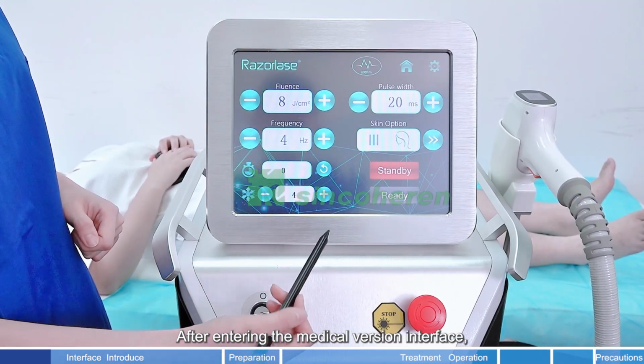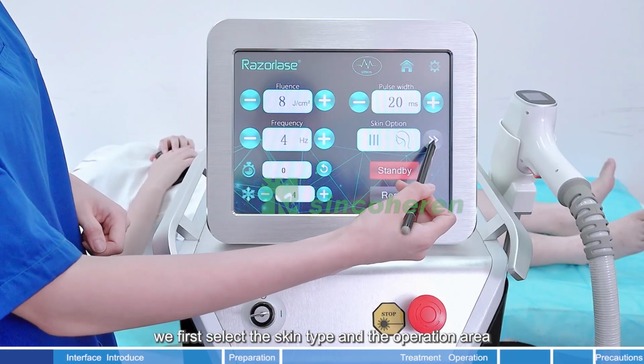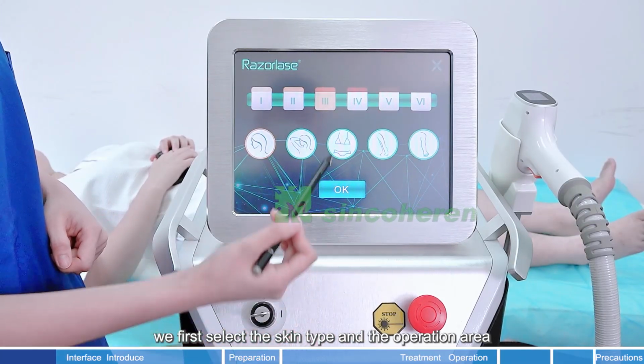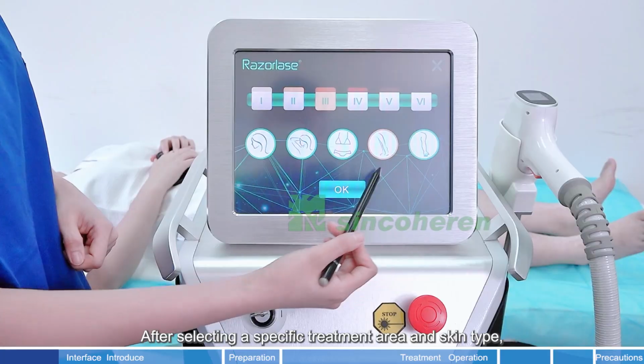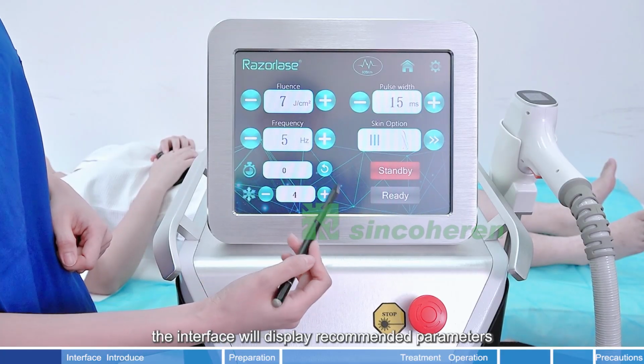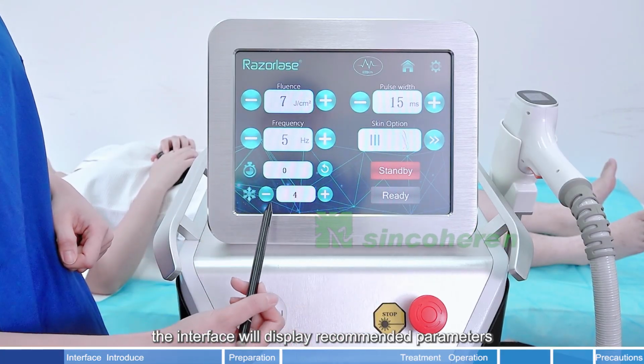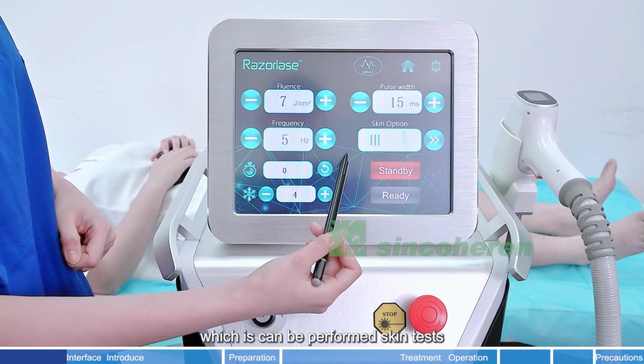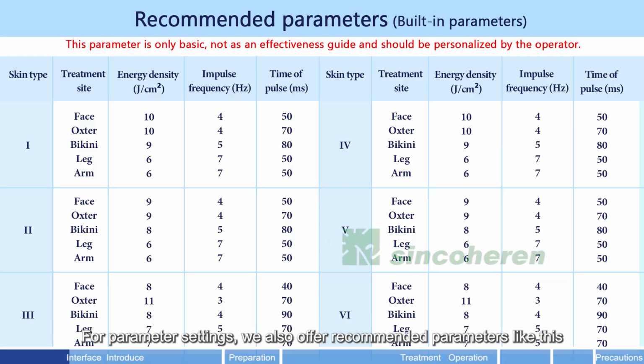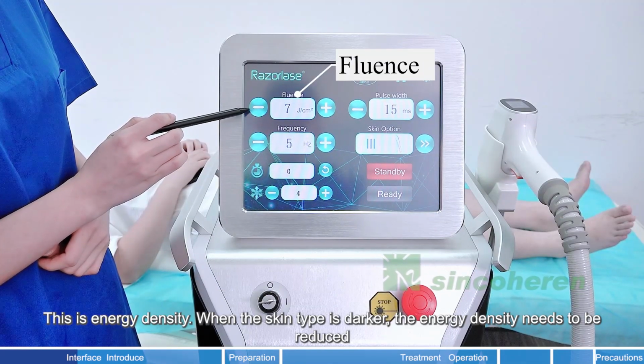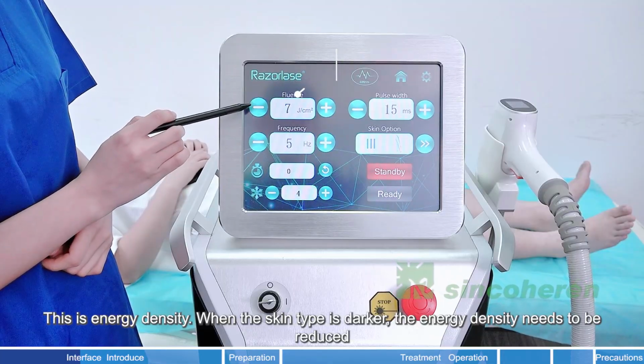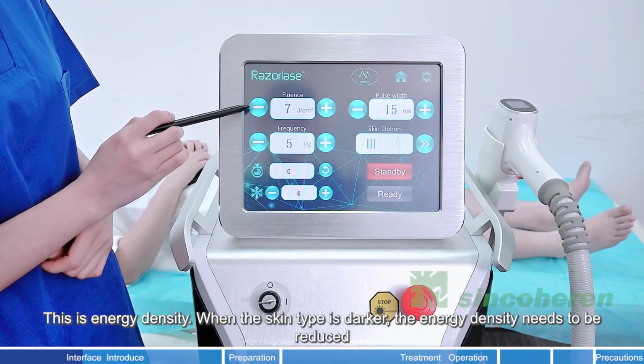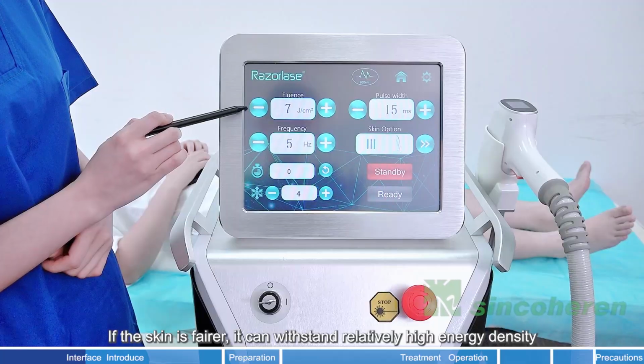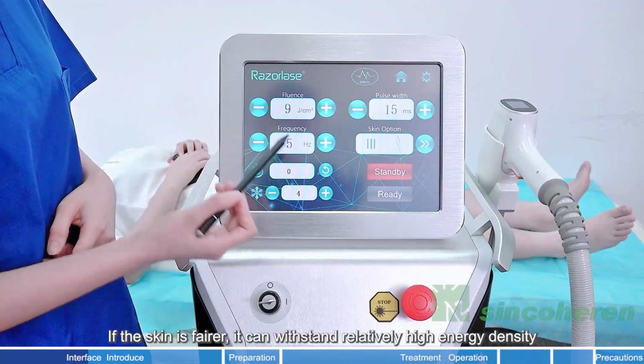After entering the medical version interface, we first select the skin type and the operation area. After selecting a specific treatment area and skin type, the interface will display recommended parameters, and a skin test can be performed according to the parameters. For parameter settings, we also offer recommended parameters like this. This is energy density. When the skin type is darker, the energy density needs to be reduced. If the skin is fairer, it can withstand relatively high energy density.